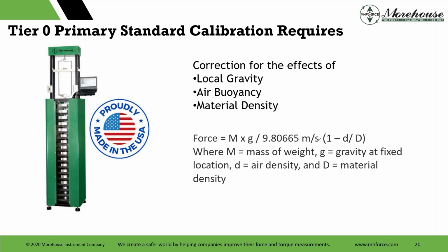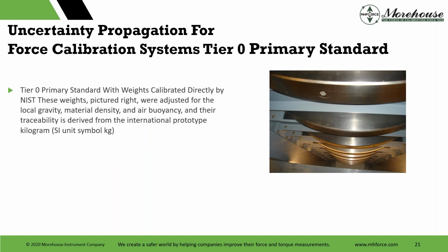On our website, there is a guidance document and an Excel sheet that will do mass to force, where you can enter all this in and it does the calculations for you on what your target should be. In that case, you still do need to know the material density, air buoyancy, and local gravity, and there's the formula for that. And then here's a view down from our machine. Weights pictured were adjusted at NIST, and traceability is still derived from the International Prototype Kilogram, the SI symbol.